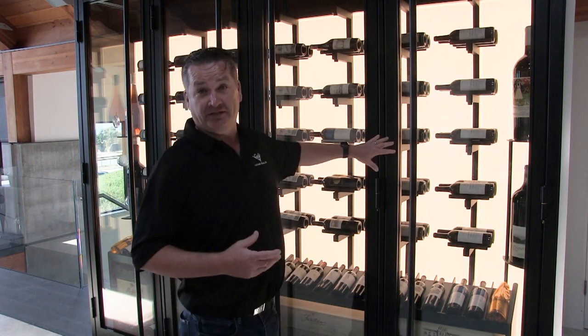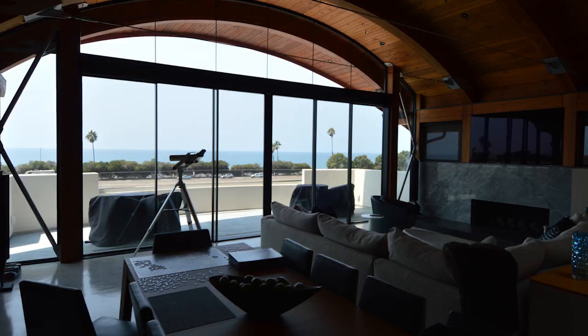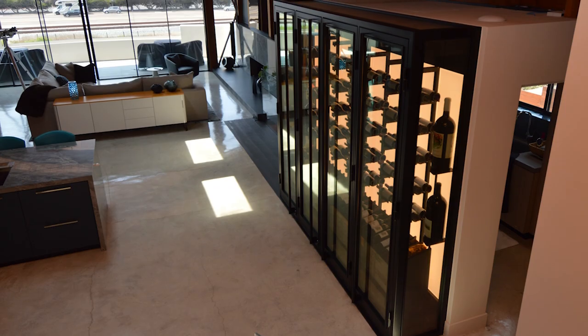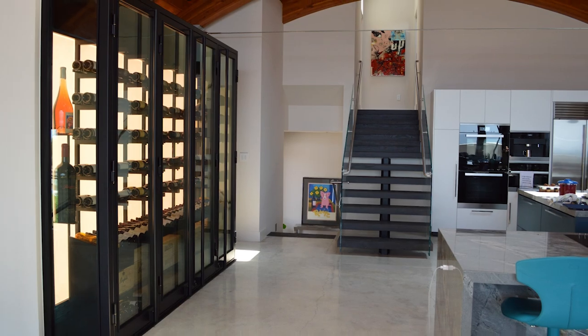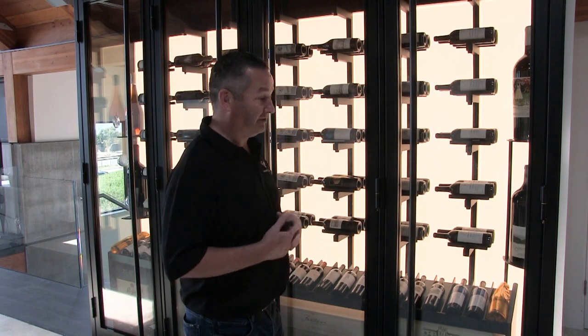We're at a 55 degree room out here and you have an 80 degree day with some humidity — there's a chance for condensation. That's why we're very big on dual pane thermal insulated glass. Everything's weather stripped and sealed. We basically built a big refrigerator in there and we want to keep it at temperature, so we want to keep the moist warm air out so it does not condensate on the glass or your steel.